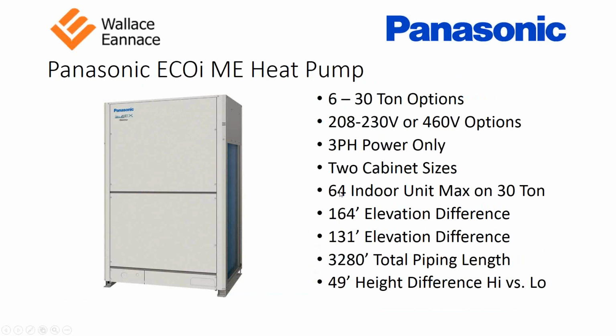So you can connect 64 indoor units max to the 30 ton, and the elevation differences on the roof versus on the ground are the same, 164 versus 131. The total amount of piping that we can connect to the system is 3,280 feet total. And the height difference for the highest indoor unit versus the lowest indoor unit is the same. It's 49 feet.